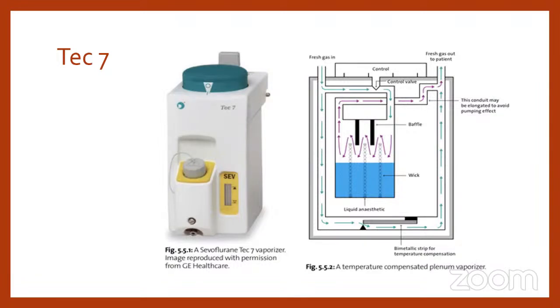It has greater accuracy from 0 to 5, and in some vaporizers up to 8 or 10 percent. Greater accuracy of fresh gas flow is up to 5 liters per minute. At higher flow rates and higher dial settings, there is a decrease in output. The innovative anti-spill system in the Tec vaporizer limits the movement of liquid agent if the vaporizer is tilted or inverted. Even if you invert the vaporizer, the liquid will not come out of the reservoir. That is a safety mechanism incorporated so that transport of the vaporizer can be safer.